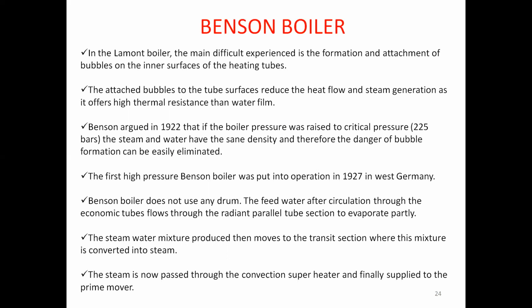The bubbles attached to the tube surface reduce the heat flow and the steam generation, as they offer higher thermal resistance than the water film. That is the reason we consider the Benson boiler. Also, the pressure here can go up to 225 bar. The first high pressure Benson boiler was put into operation in 1927 in West Germany.